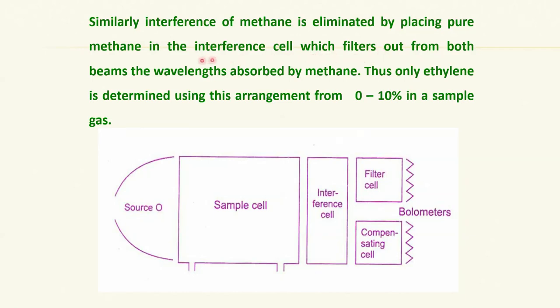It is something like cancelling each other. Interference of methane also can be similarly eliminated by placing pure methane in the interference cell. Only ethylene is being determined using this arrangement from 0 to 10 percent in a sample gas. You should note down the percentage. We are not talking about the ppm level or milligram level or trace ultra trace. We are talking about percentage. That is why such instruments are used in the process industries petrochemical complexes.